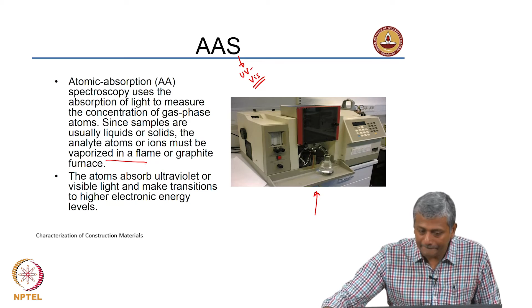So, this is the typical setup. You have a hollow cathode lamp, which is a source that produces light with the intensity of ultraviolet or visible light. Then it is sent through a lens, because we want to ensure that we have a convergent beam that goes right through your atomized sample. Again, we want to ensure that all the intensity coming out of the atomized sample is directed towards a detector.